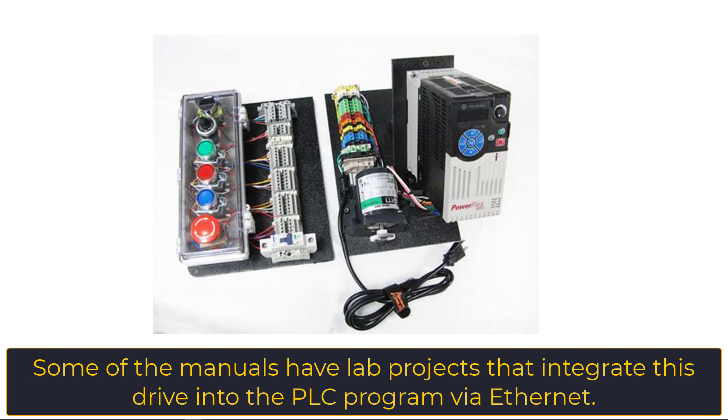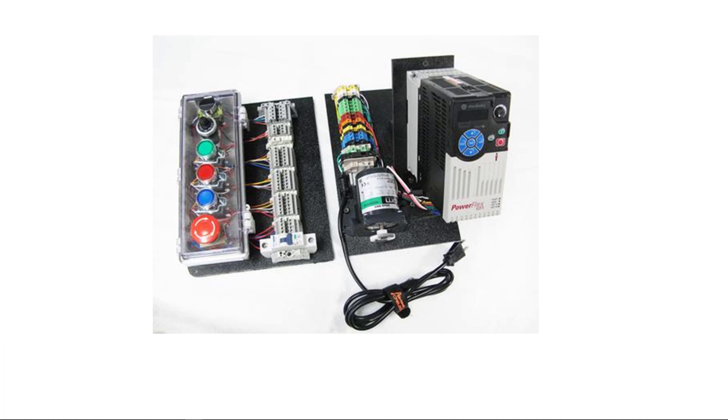We also have an operator station starting at the bottom. We have an emergency stop push button, press and twist to release with two normally closed contact blocks. And then we have three backlit momentary push buttons and all three of those have one normally open and one normally closed contact block.